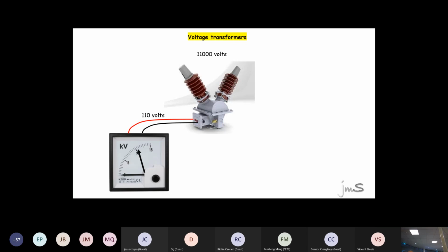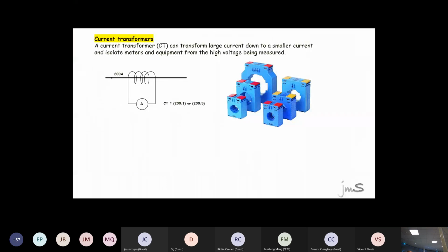Let's look at the CT. The CT does exactly the same. A CT's purpose is to measure high currents safely. Now guys, you all have clamp meters. This is actually a clamp meter, or what it is. But this clamp meter we can't open. It's a solid one which is always on a bus bar.